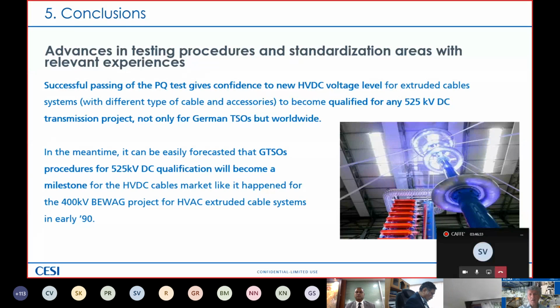And this to become qualified for any 525 kV DC transmission project, not only for the German TSOs, but worldwide. In the meantime, we can easily forecast that the German TSO's procedure, the one I presented to you for the 525 kV DC qualification, will become a milestone for the HVDC market, like it happened for the 400 kV BEWAG project, as I told you, for the HVAC extruded cable system in the early 90s. I think this is a very big step forward, this 525 kV DC project.